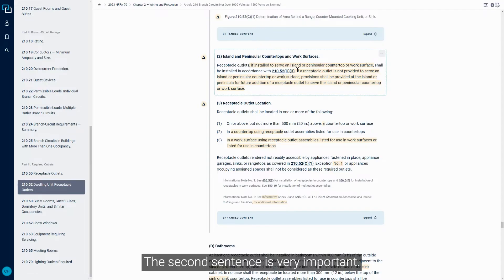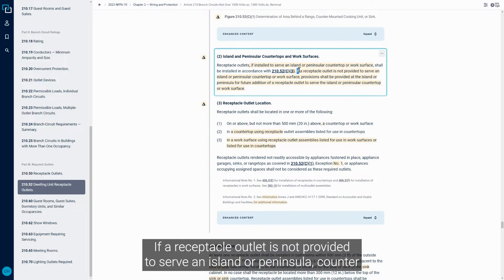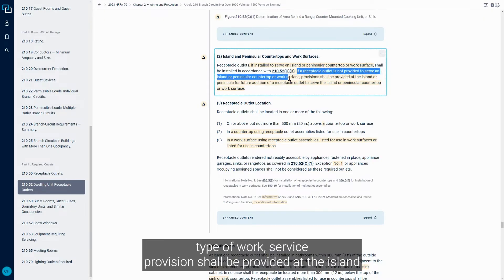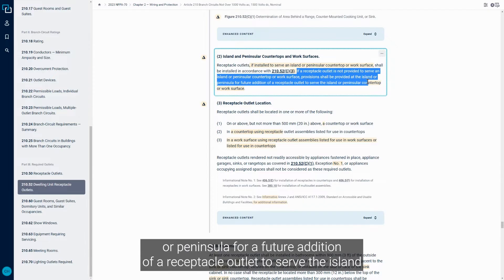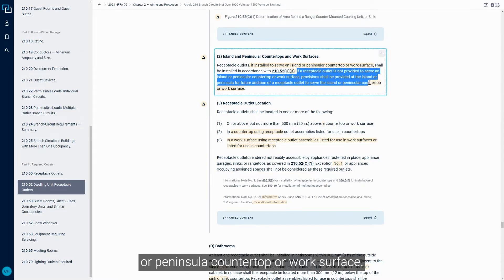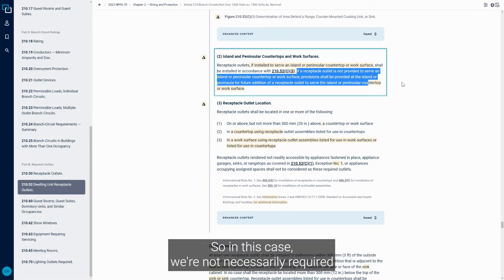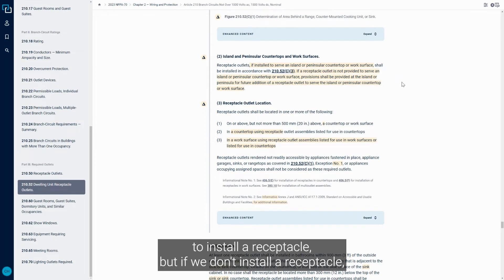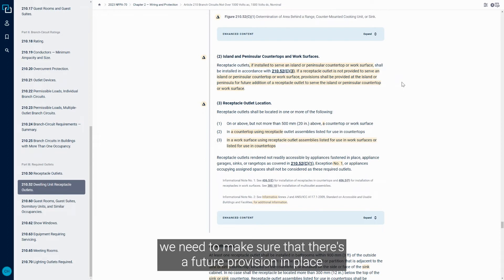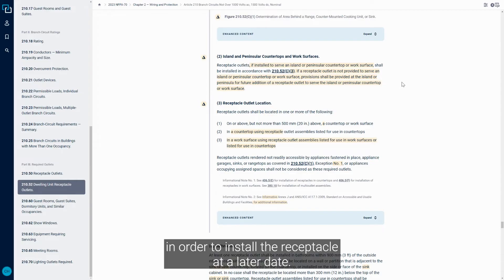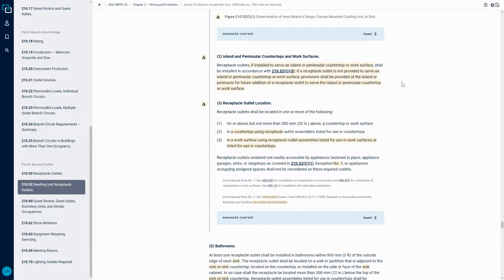This second sentence is very important. If a Receptacle Outlet is not provided to serve an island or peninsula countertop or work surface, provision shall be provided at the island or peninsula for a future addition of a Receptacle Outlet to serve the island or peninsula countertop or work surface. So in this case, we're not necessarily required to install a Receptacle.